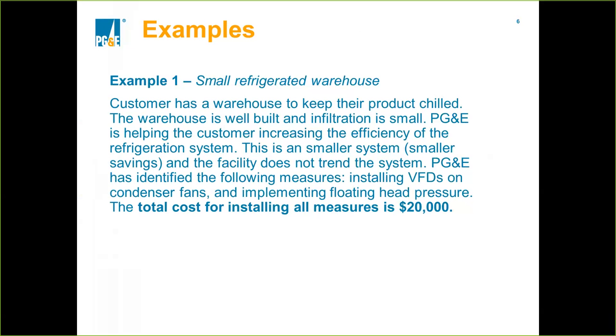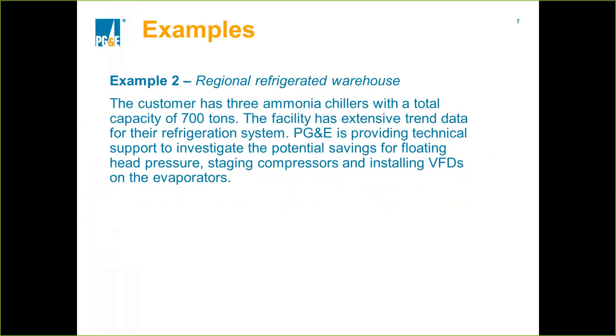The PG&E engineer has found a couple of measures that might save energy: installing VFDs on the condenser fans and implementing floating head pressure. The total cost for the measures is estimated at $20,000. In the second example, the key is how to run a calculation with more detailed inputs. The system is bigger — they have three compressors with a 700-ton capacity in total — and they have a lot of trend data for that refrigeration system. PG&E is investigating potential savings for floating head pressure, staging the compressors, and installing VFDs on the evaporators.